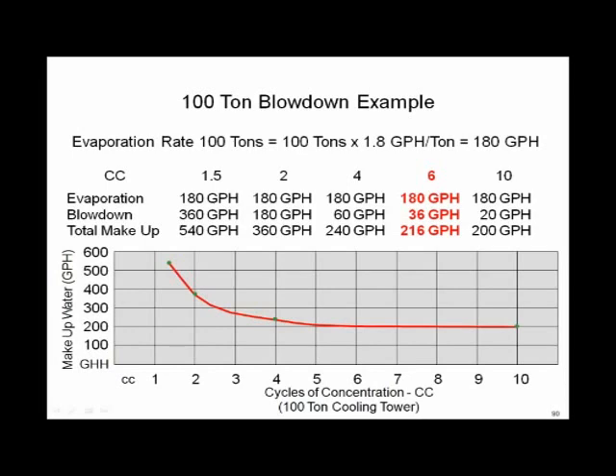So this is a plot of the makeup water required in gallons per hour versus cycles of concentration. And the message is, at 2 cycles of concentration, remember the evaporation rate of 180 gallons per hour is exactly equal to the blowdown rate of 180 gallons per hour, so we need 360 gallons per hour on a 100-ton load to maintain 2 cycles of concentration.